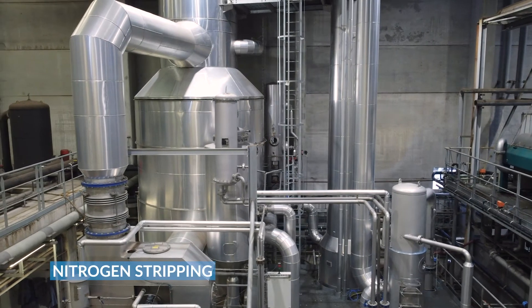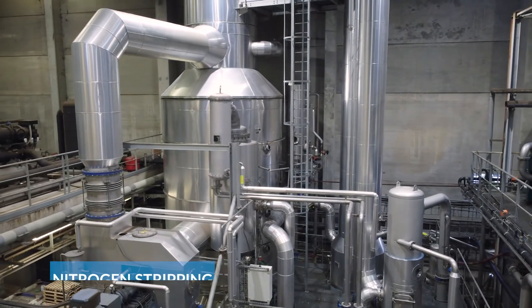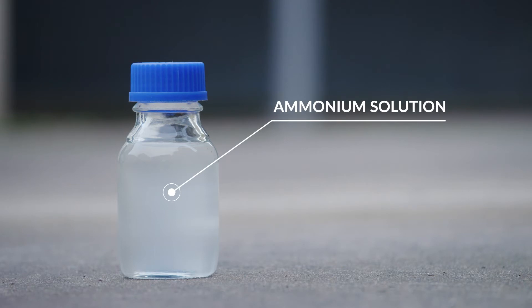Because of the elevated temperature during evaporation, dissolved nitrogen escapes the liquid as ammonia gas. When this cools down, it condensates with water vapor as a 12% ammonium solution. This solution is reused for cleaning of flue gases of a nearby incineration plant.